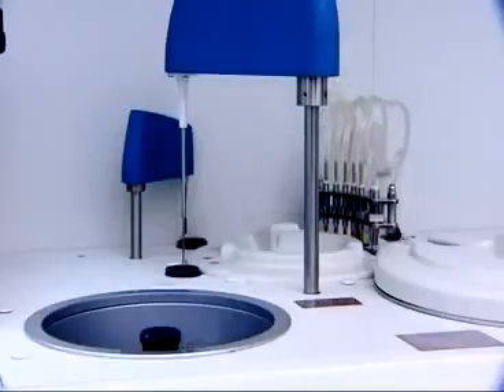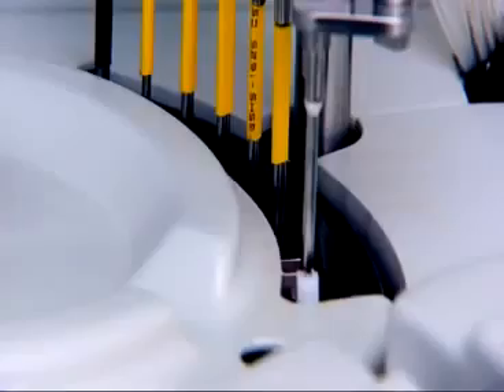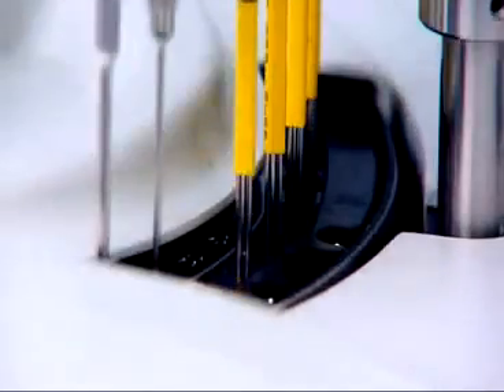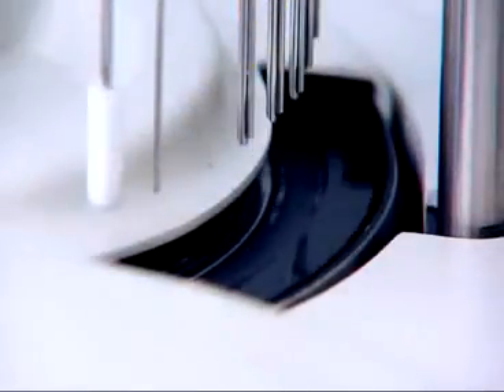This results in a much shorter payback on investment. The 8-stage onboard cuvette wash station ensures complete cleaning and drying of each cuvette prior to its use. Blank absorbances of each cuvette are checked to ensure each cuvette passes the necessary blank absorbance criteria.